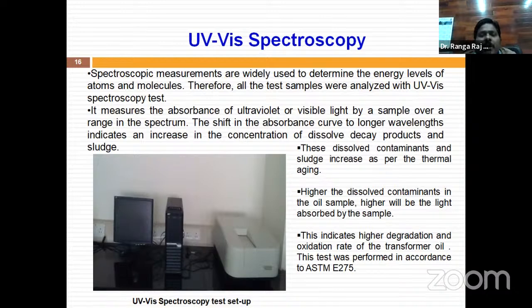We use that coefficient as a parameter to decide the aging of the oil. If the oil is aged, say 30 or 40 years in a transformer, there will be a large amount of particles, ash, dust, and it becomes completely degraded oil, so it absorbs more light. The absorption coefficient is higher compared to fresh oil, so we compare the absorption coefficient of fresh oil and aged oil through this test, and based on that comparison we decide the current health status. This test is performed according to ASTM E275.